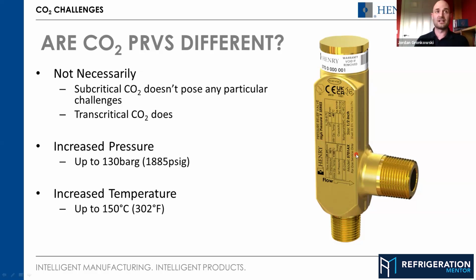Increased temperature obviously goes hand in hand with the pressure as well. Again, that comes back to affecting the seal material. Make sure the seal material is appropriate for the temperature range it's going to be working at. I've put 150, but you could even get higher than that. And the other consideration from a design point of view with temperature is the spring, because if the valve is in a high temperature environment and you haven't selected the correct spring design or materials or pre-stressed it enough, it can actually lose tension due to the temperature over the life of the valve, which makes the valve open early, which obviously is something we don't want.